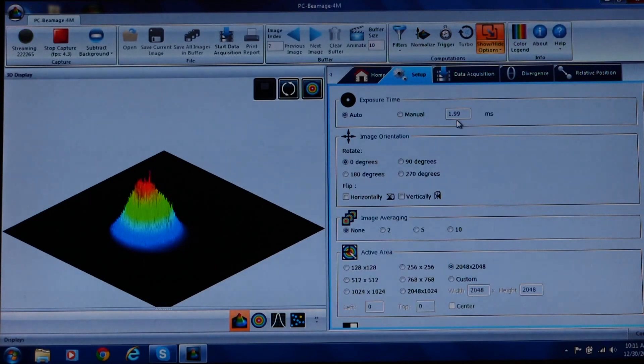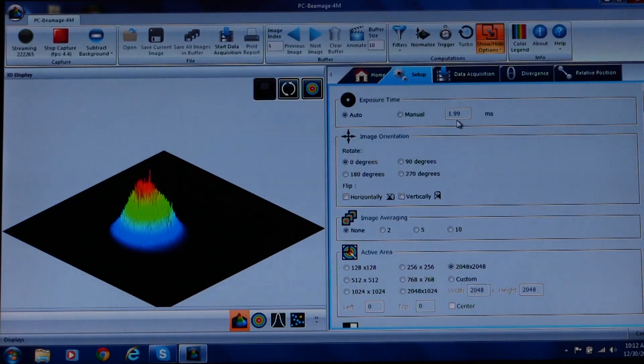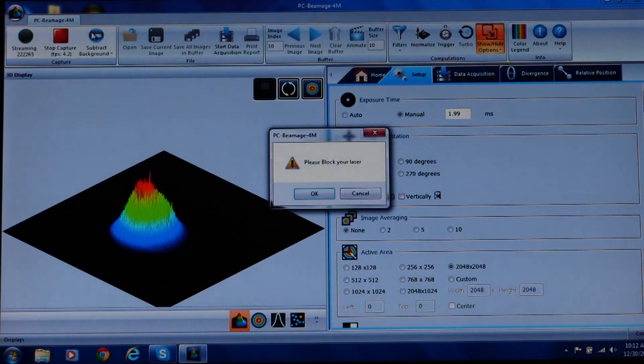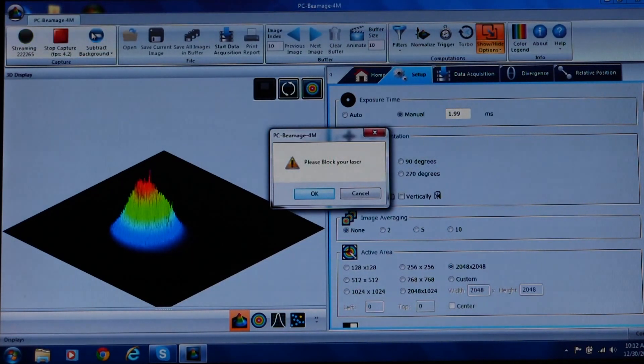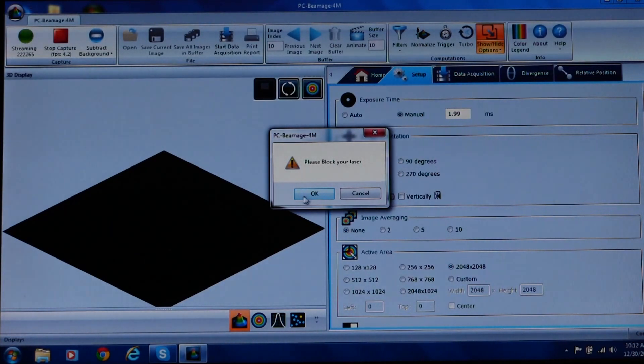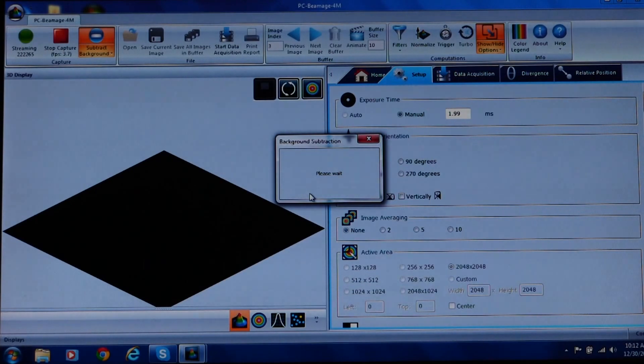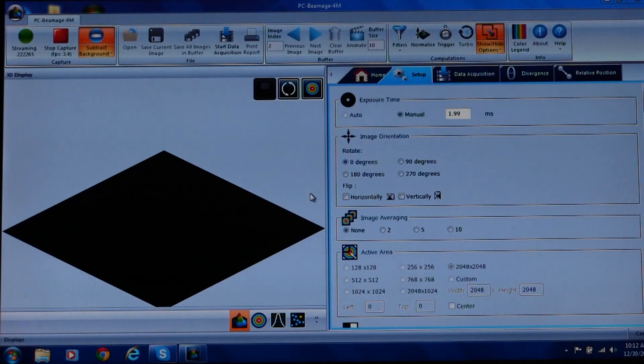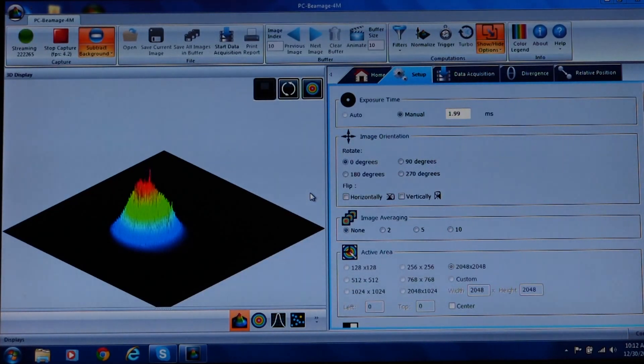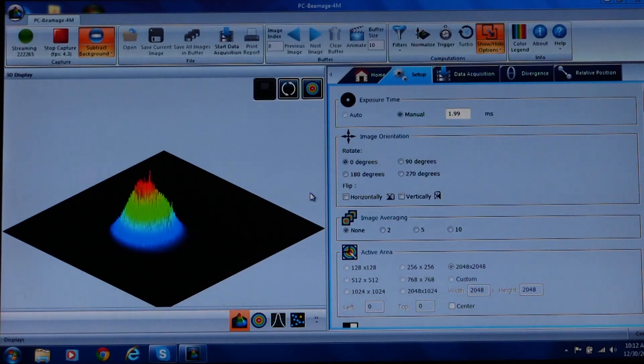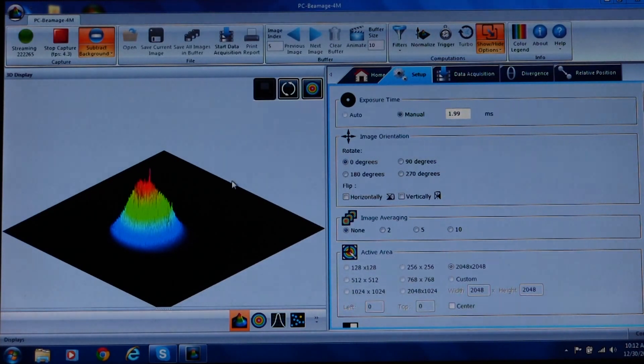Let's move on. The next thing you need to do is to subtract the background radiation. So we'll click on the blue subtract background button. You will get a window that asks you to block the beam. So, block the beam and then press OK. Another window appears that asks you to please wait. Once this disappears, you can remove the beam block. Note, make sure to use a beam block material that is totally opaque and does not transmit the laser light.